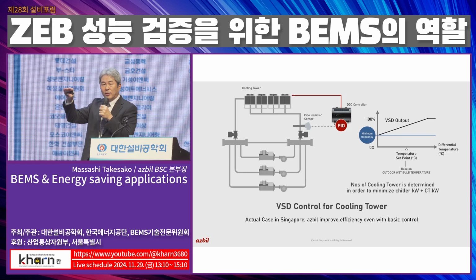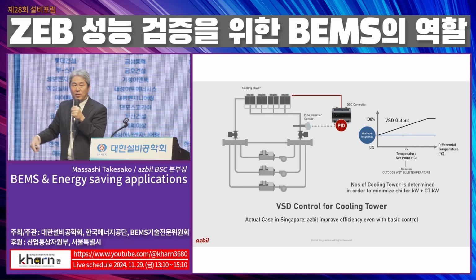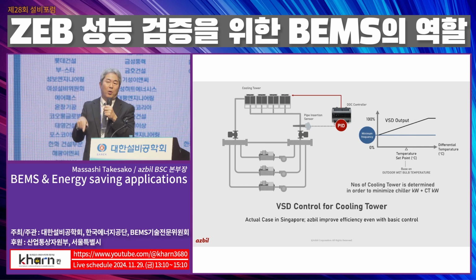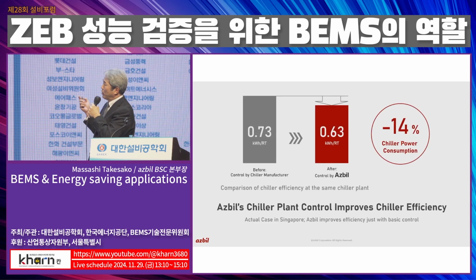What is the best fan speed to maximize the benefit of the entire chiller plant? So we cannot think only of the fan energy consumption. We also need to think that the entire system energy efficiency has to be achieved at the best operating point. That is also one of the important points. Then as a result, this is just an example, 14% saving can be expected from this very basic control.